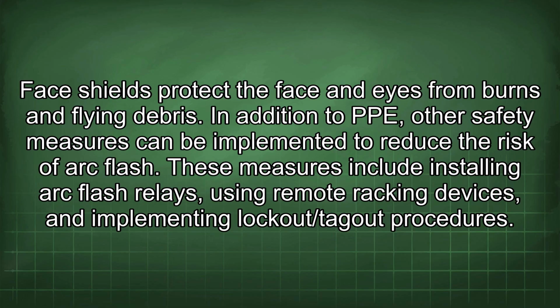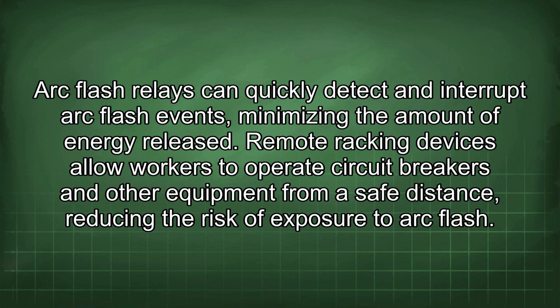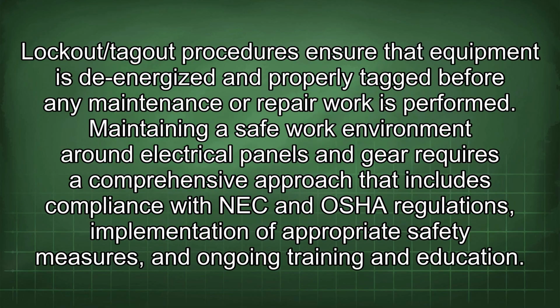In addition to PPE, other safety measures can be implemented to reduce the risk of arc flash. These measures include installing arc flash relays, using remote racking devices, and implementing lockout/tagout procedures. Arc flash relays can quickly detect and interrupt arc flash events, minimizing the amount of energy released. Remote racking devices allow workers to operate circuit breakers and other equipment from a safe distance, reducing the risk of exposure to arc flash. Lockout/tagout procedures ensure that equipment is de-energized and properly tagged before any maintenance or repair work is performed.